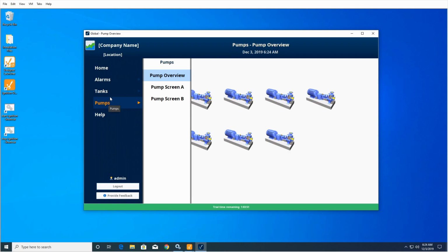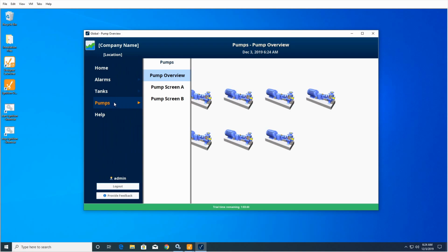Another option I had, that I have working but stripped out of this demo, is some alarm counters. So when you're configuring the table of items, you can say, all right, I want to search for alarms on this tag provider and this display path. Show me all the pump alarms. And then, if you have unacknowledged alarms, they'll be red, say, 5 unacknowledged alarms. Or if all your alarms are acknowledged, then it'll show 4 acknowledged alarms in yellow.